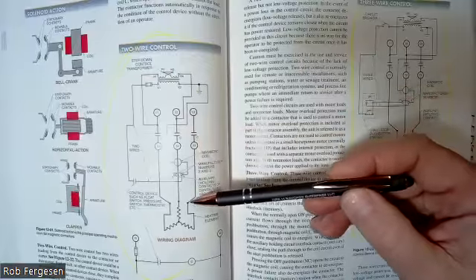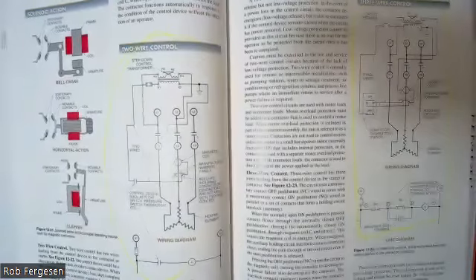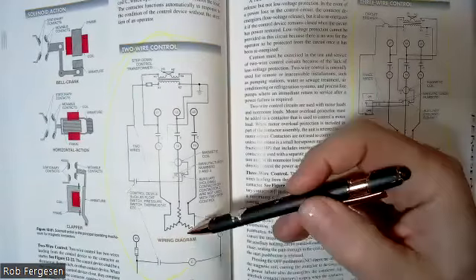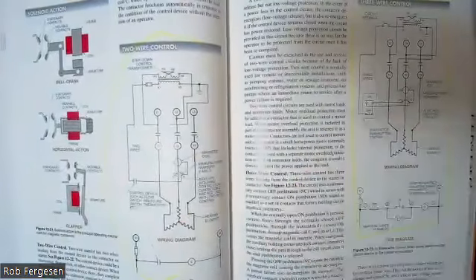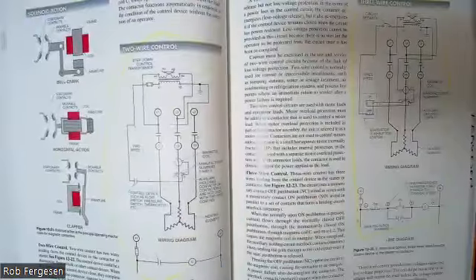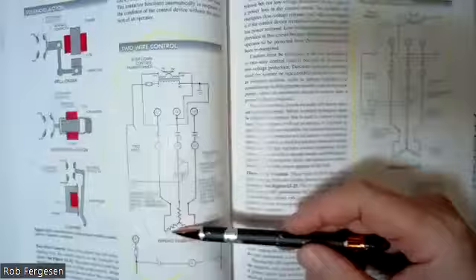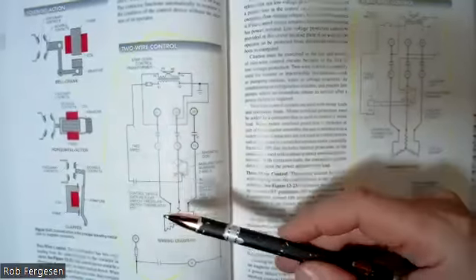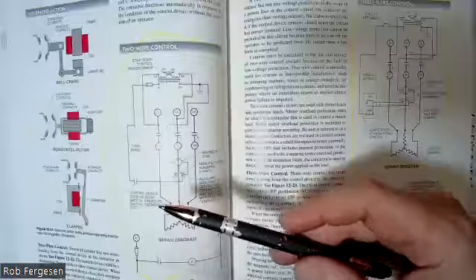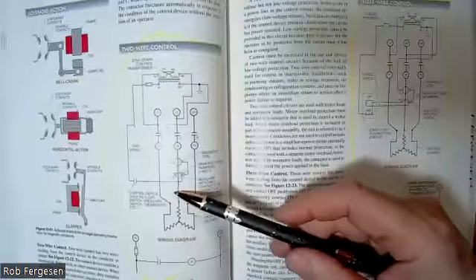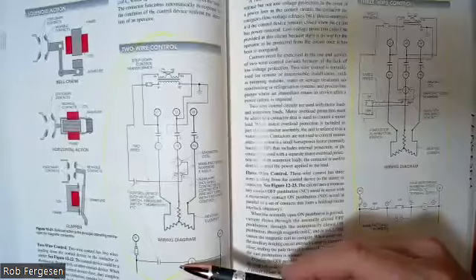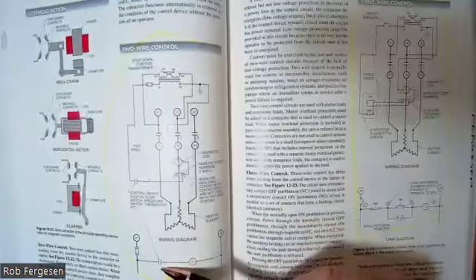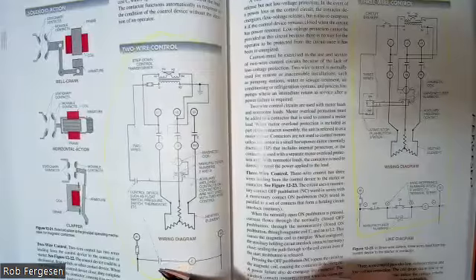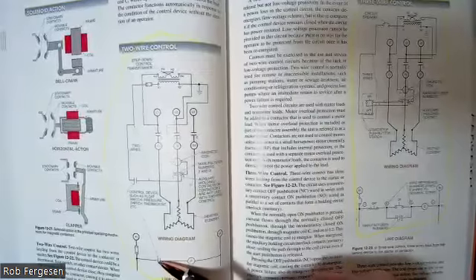And then they show you these lines going down, in this case, to a heating element set up in a Y configuration. So there are 3 heavy-duty heating coils that all tie together in the middle to give you a 3-phase Y configuration. So this is a really typical 3-phase power circuit for a simple contactor circuit. But they don't tell you how to control it until you look down here.